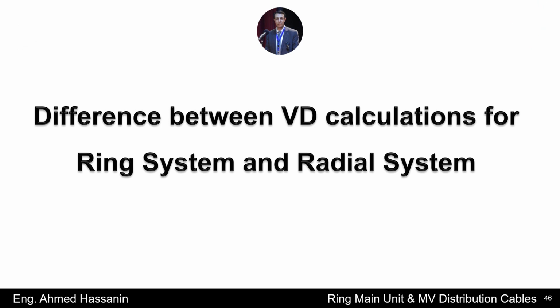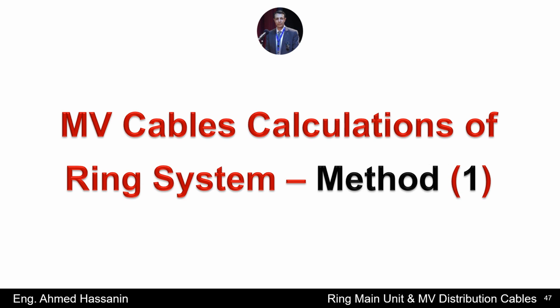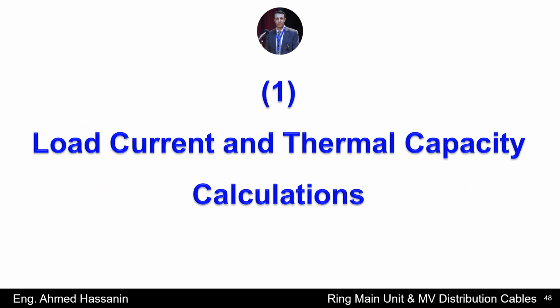I will tell you and explain the difference between the calculations of voltage drop for the ring system and radial system. In detail and step by step, I will explain two important methods for calculating the medium voltage cables of the ring system. In the first method, in detail and step by step, I will start by calculating the load current and thermal current for the medium voltage cables of the ring system.